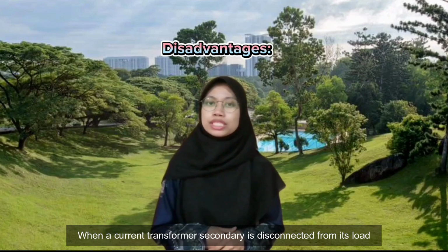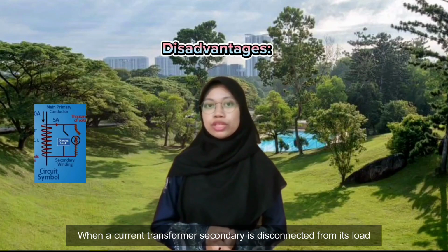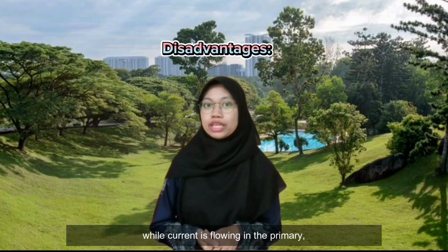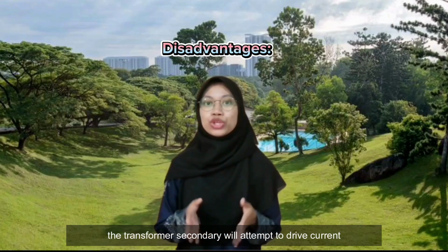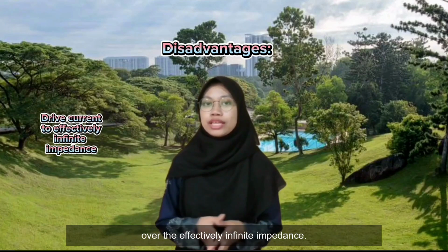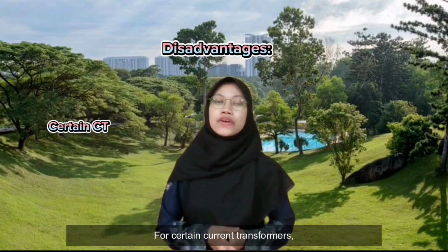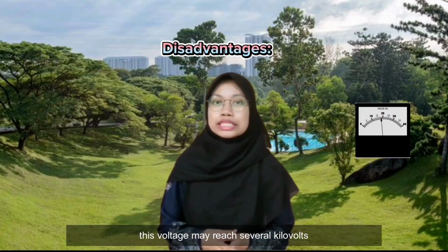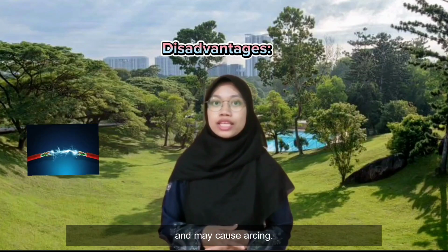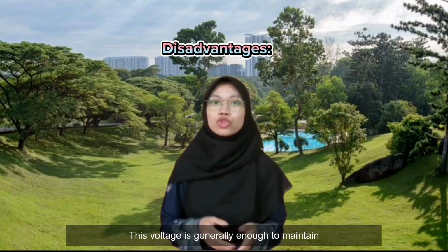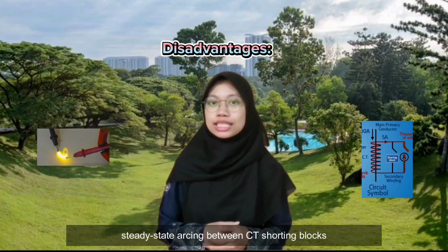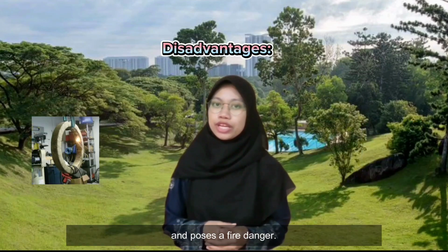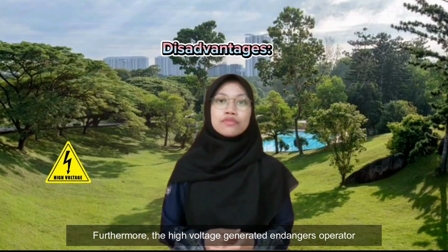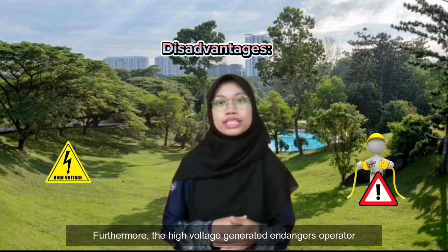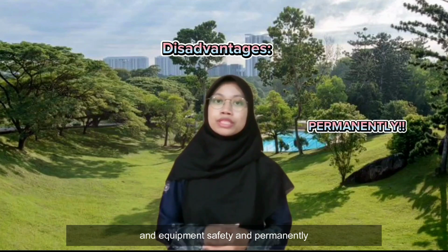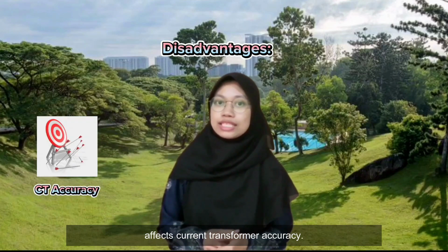When a current transformer secondary is disconnected from its load while current is flowing in the primary, the transformer secondary will attempt to drive current over the effectively infinite impedance. For certain current transformers, this voltage may reach several kilovolts and may cause arcing. This voltage is generally enough to maintain a steady state arcing between CT shorting blocks and poses a fire danger. Furthermore, the high voltage generated endangers operator and equipment safety and permanently affects current transformer accuracy.